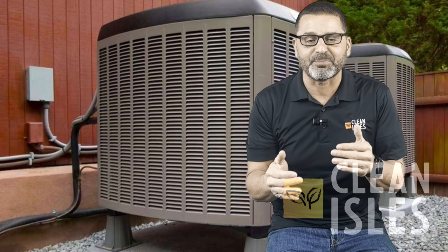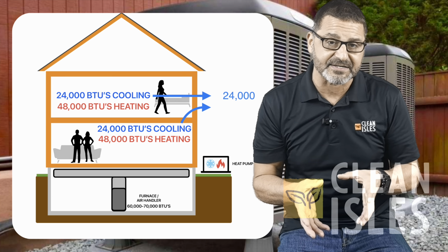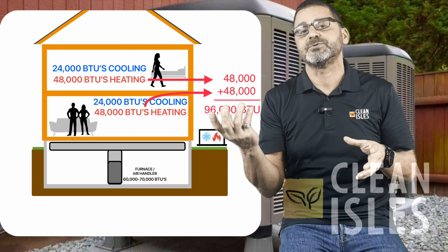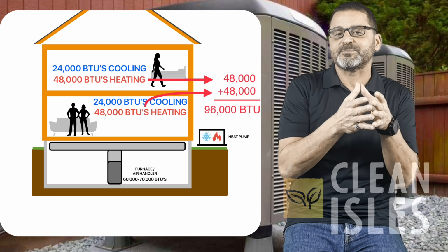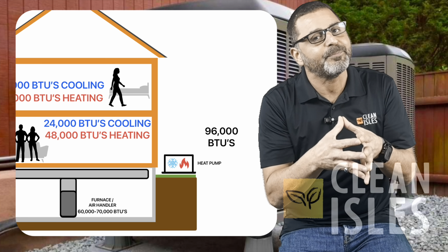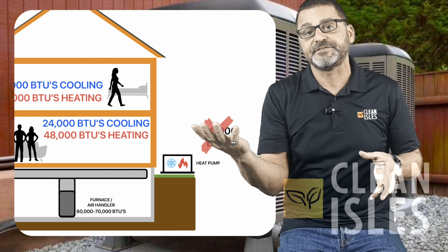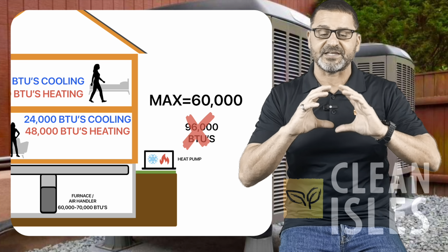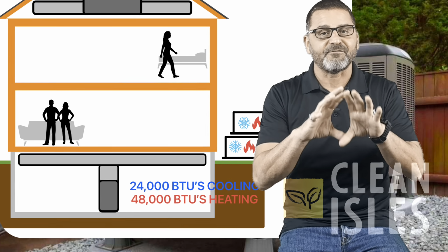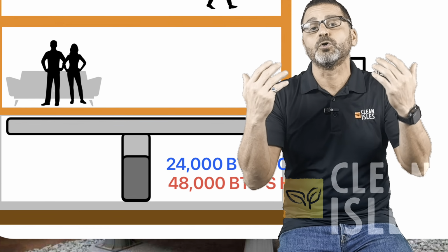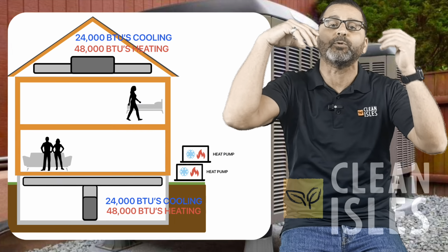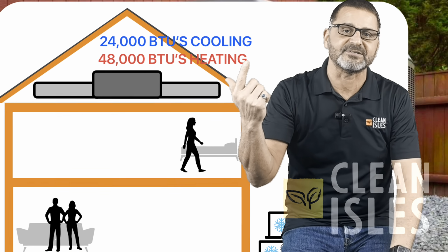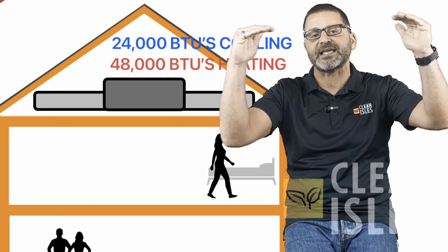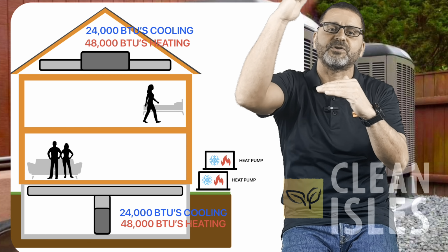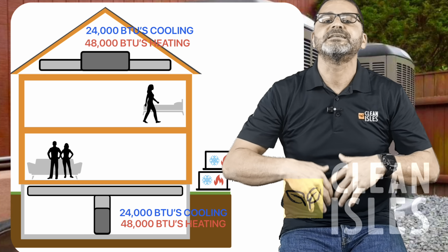So let's take that same example and make it 2 stories. Now the house needs 48,000 BTUs to cool and 96,000 BTUs to heat. The problem is that heat pumps, the max of a residential cold climate heat pump is 60,000 BTUs, a 5-ton. So we would actually have to double it. So I'd have to install in the basement a 48,000 BTU system, and that would provide heat and cool to only the first floor. And then in the attic, I would put in another 48,000 BTU system, and that will supply only the second floor. So 48 up here, 48 down here, that'll give us the 96,000 BTUs to heat the entire house. So I say all that to say this.